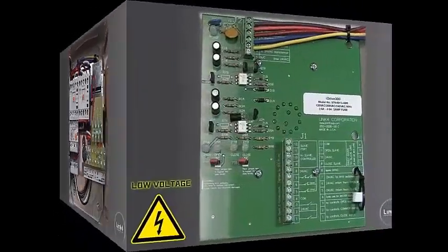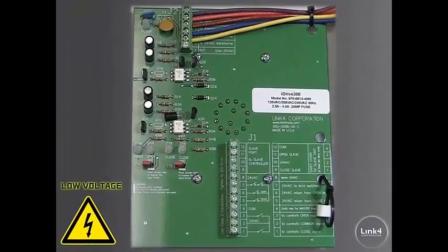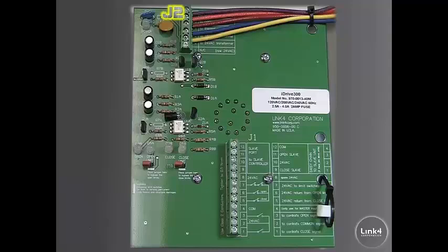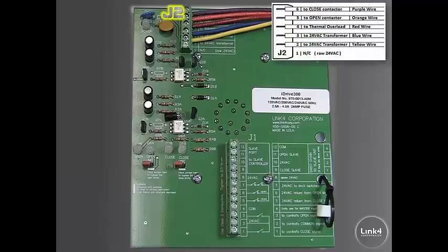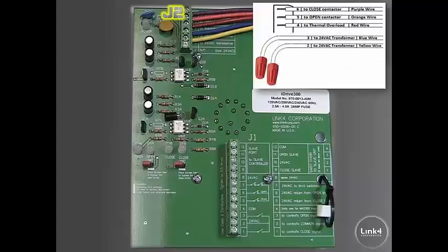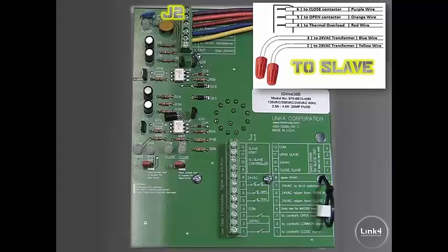On the low voltage side, which consists of the J2 portion of the circuit board, you have the close, open, and thermal overload wiring going to it, as well as two 24 volt transformer wires. To slave this device, you would disconnect the two 24 volt transformer wires and cap them independently.